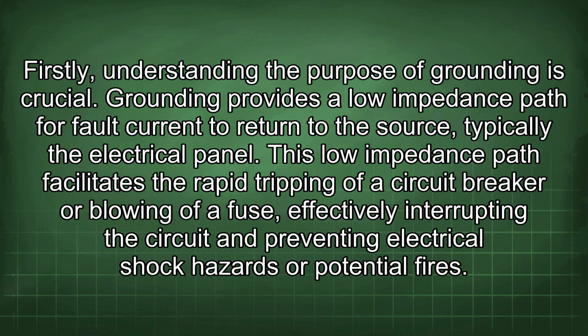Firstly, understanding the purpose of grounding is crucial. Grounding provides a low impedance path for fault current to return to the source, typically the electrical panel. This low impedance path facilitates the rapid tripping of a circuit breaker or blowing of a fuse, effectively interrupting the circuit and preventing electrical shock hazards or potential fires.